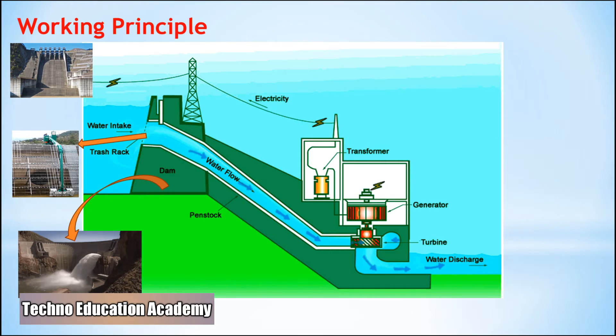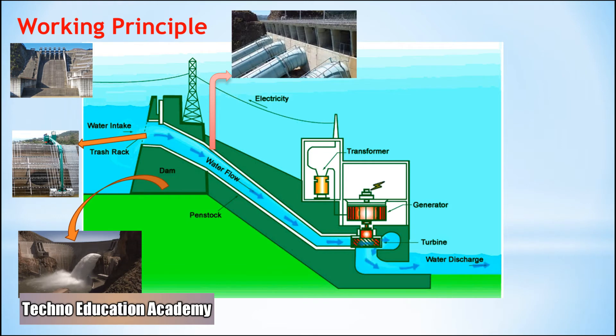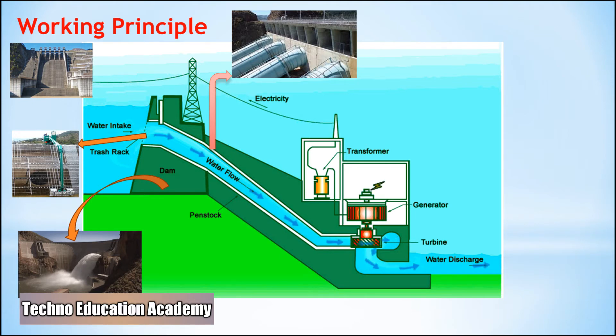The next component is the penstock and tunnels. Penstocks are the pipes which carry water from the reservoir to the turbine inside the power station. They are usually made of steel and are equipped with a gate system. Water under high pressure flows through the penstock — one end is connected to the dam side and the other to the turbine side. Tunnels serve the same function as penstocks and are used when an obstacle such as a mountain is present between the dam and the power station.